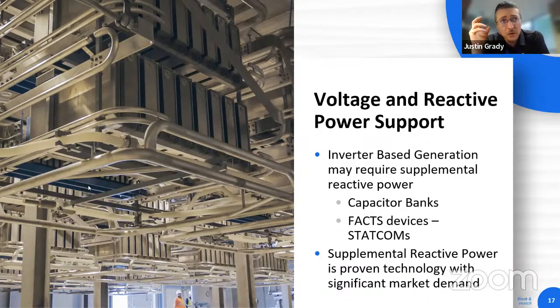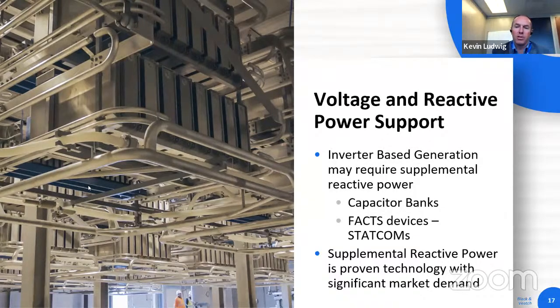So the generator itself is no longer being spun by a turbine - is it spinning because of the electrical influence of the transmission grid pushing back on it? Correct. So essentially that generator is still spinning at the frequency at which the power system operates, which would be 3,600 RPMs. You've got a significant amount of mass spinning at that revolutions per minute, and that adds inertia.